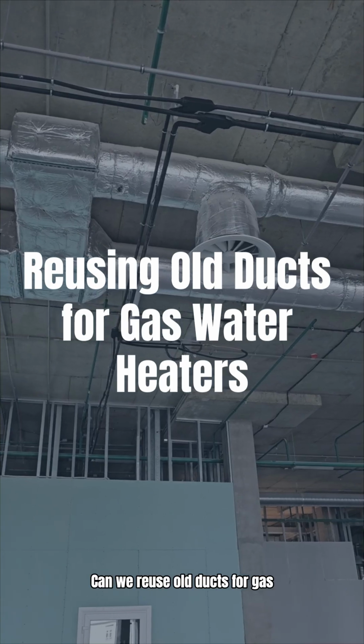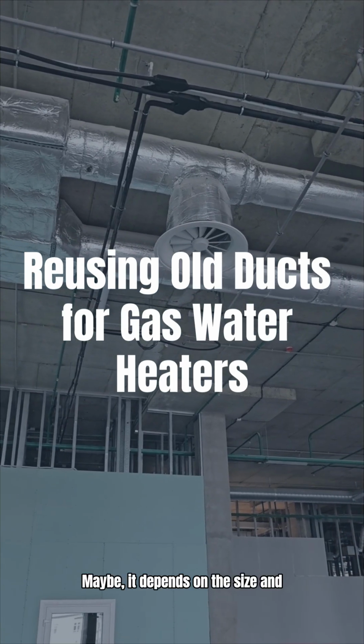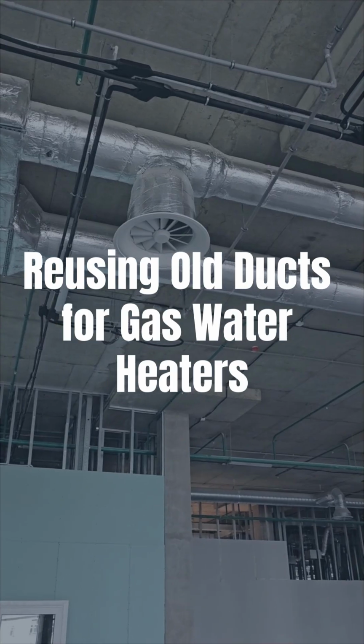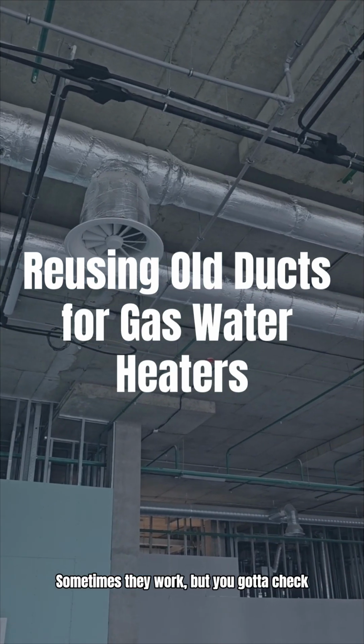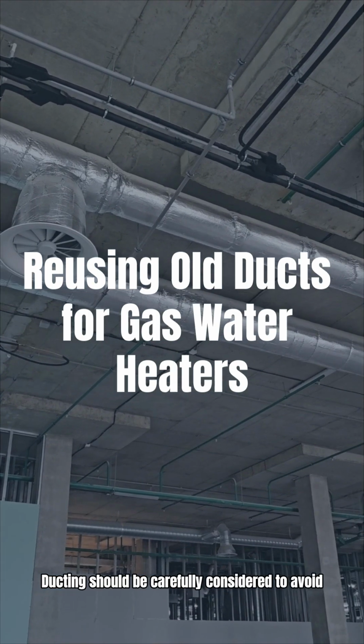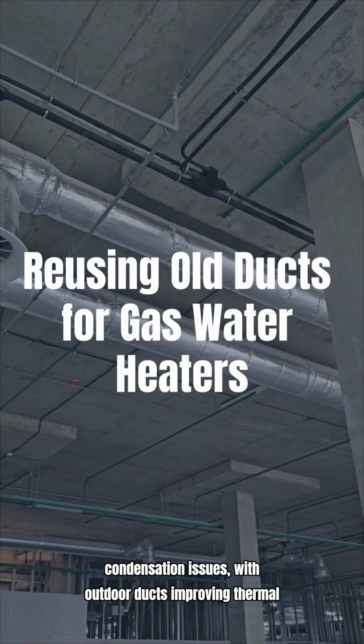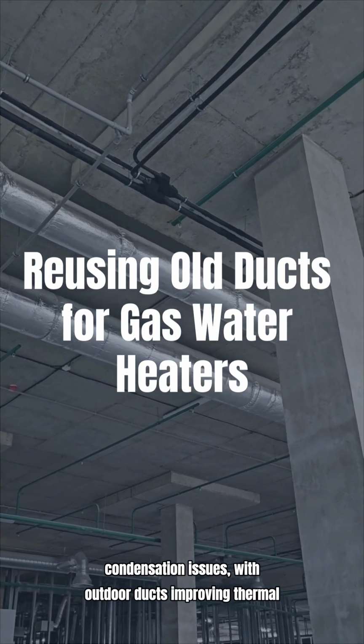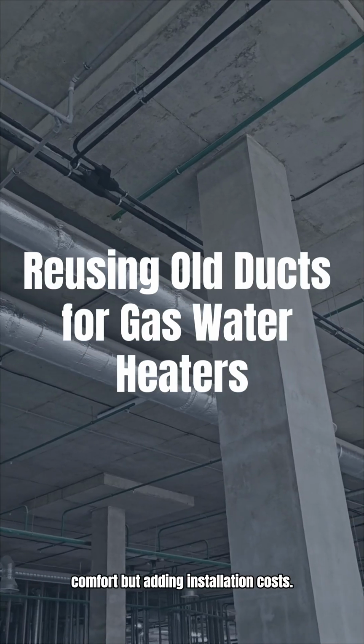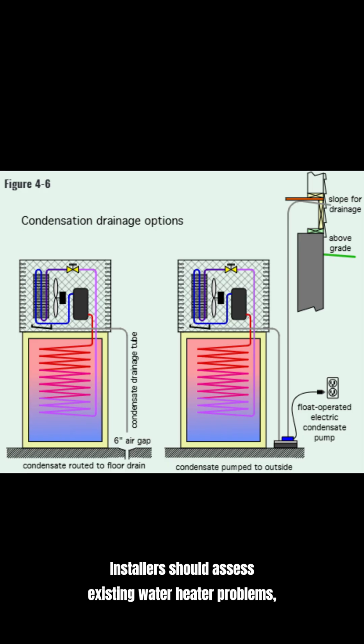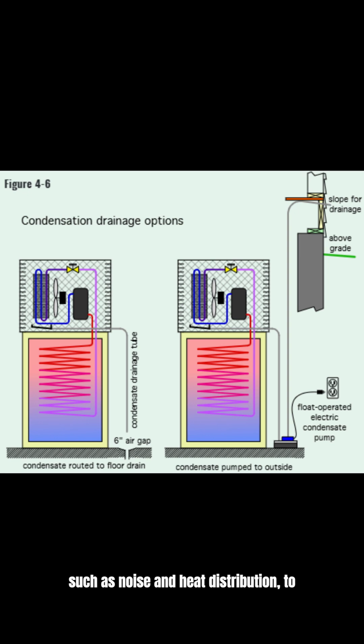Can we reuse old ducts for gas water heaters? Maybe. It depends on the size and length. Sometimes they work, but you gotta check the specs first. Ducting should be carefully considered to avoid condensation issues, with outdoor ducts improving thermal comfort but adding installation costs. Installers should assess existing water heater problems, such as noise and heat distribution, to enhance the placement of HPWHs.